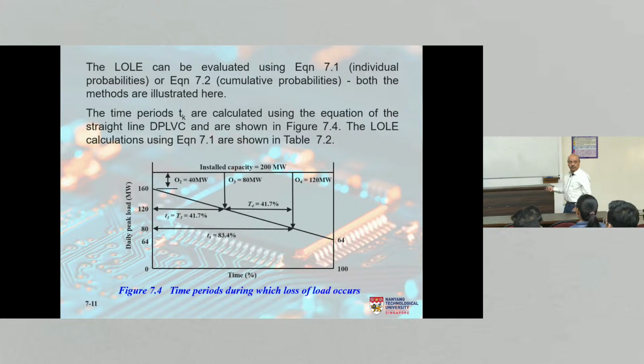Okay. Now I mentioned the cumulative probability, so I think we can use the same figure to even look at cumulative probability. So what happens when the outage is 80 megawatt? We are going to use uppercase T3, which is small t3 minus T2, but there is no T2, T2 is 0. Therefore, it will be 41.7 minus 0, so it will still be 41.7. But for the 120 megawatt out, we have the small t4 and small t3. Therefore, the difference of the two is t4 minus t3, which is uppercase T4, which also happens to be 41.7%. So that's how we will do the cumulative probability table and calculate the risk.